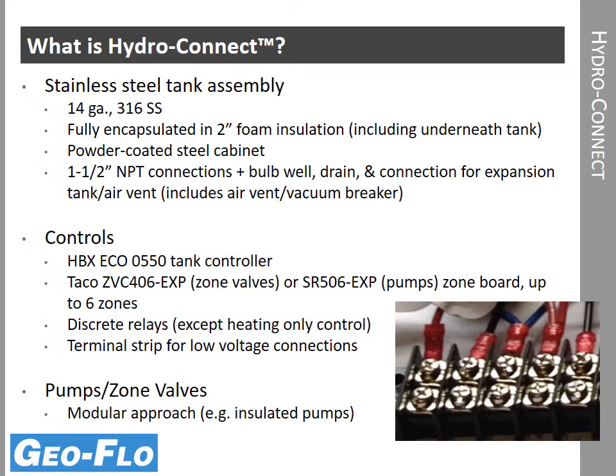As far as controls go, as I mentioned earlier, there really isn't one control that does the entire job, especially for heat pump systems. So we're combining what we think are the best of both worlds with an HBX tank controller and a Taco zone board. The HBX tank controller is an Eco 550. It acts as our aquastat, but has additional features as mentioned earlier, such as warm weather shutdown and outdoor temperature reset. The Taco zone panel is really a nice panel for either zone valves or pumps, but it's designed for heating. So with the addition of discrete relays, then we can make this into a system that handles both heating and cooling, and the switchover accordingly.